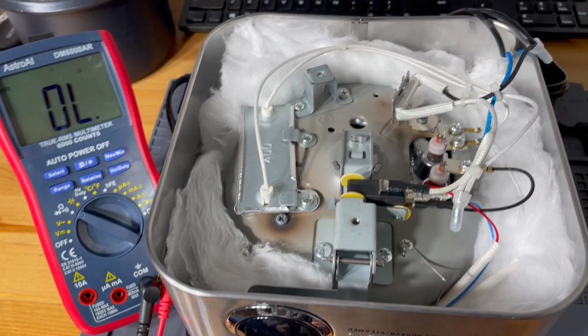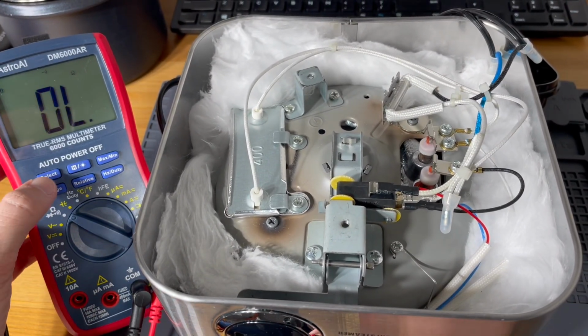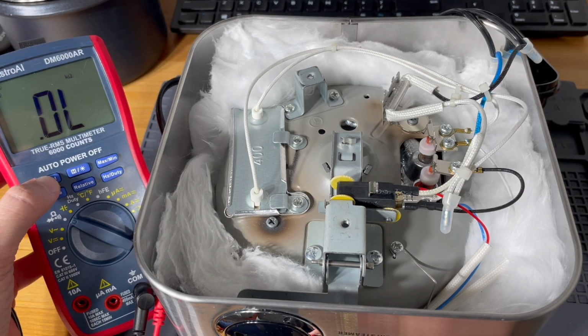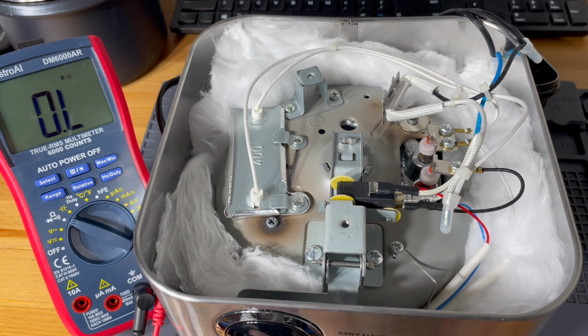Okay, so maybe a couple of things we can learn here. If I turn the meter back over to resistance, we can measure the resistance of those two heater circuits. Now I would think the resistance of the warm circuit should be much higher than the resistance of the cook circuit. The reason I say that is a lower resistance will produce more heat, so in order to get more heat for the cook circuit, I'd expect to see a much lower resistance reading in terms of ohms.